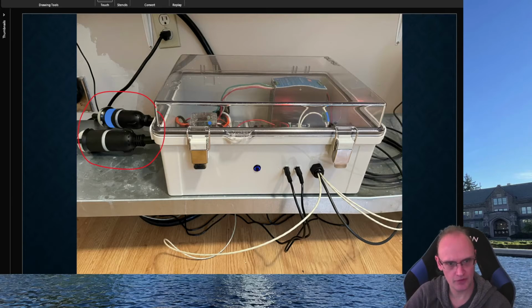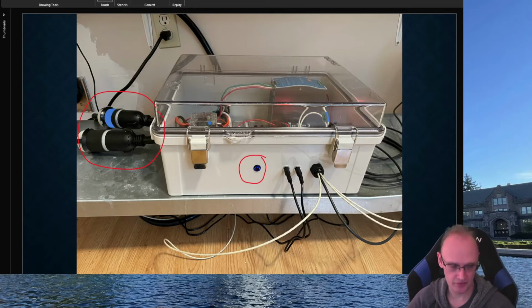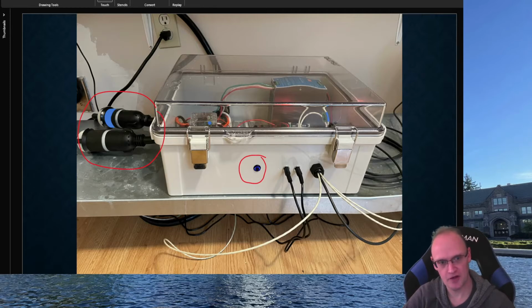And then another important consideration is this guy. This is a hardware kill switch for the high voltage part of the panel. So in the case of software failure or a sensor failure, we don't want the heating elements to come on when we don't intend for them to come on. That could be really dangerous. We don't want them to dry fire. So it's good to have this clicked off until you're in a state where you know that you want the software to switch these on and off.